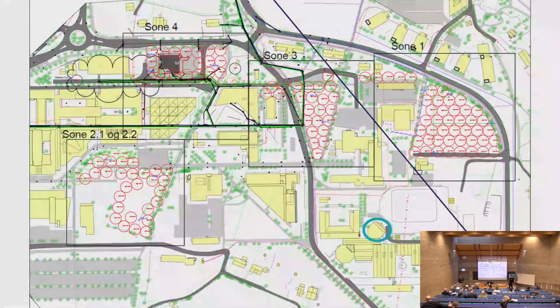What's the distance between them? There's a bit of variation, but the rule of thumb is 10 meters, and it will be down to 4 meters sometimes. But I think in this project, they've tried to have at least 15 meters between the boreholes, from the design plan. So of course, this takes up a lot of space, and as Karl Erik said, you need pipes to every borehole, and then you need to connect all those pipes and bring the fluid to the energy plant, which is up there. So there's a lot of other equipment as well.